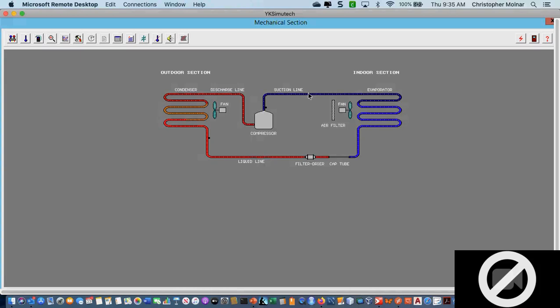That's exactly what's happening here in the evaporator. As I come out of the metering device through the cap tube, I now have that spray of liquid refrigerant — think of it equivalent to water. It goes into the evaporator, and as it absorbs heat from the space I'm trying to cool, it actually boils off inside the tubes. This boils the refrigerant off inside the tubes and it changes into a gas, which is equivalent to steam.